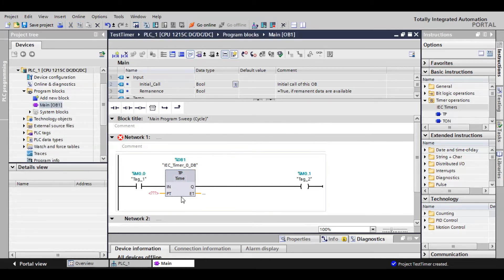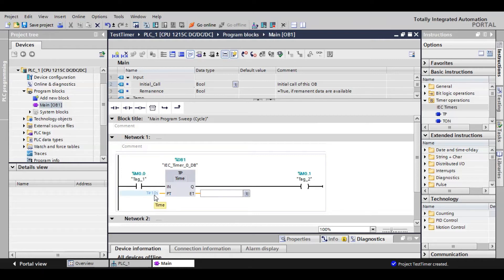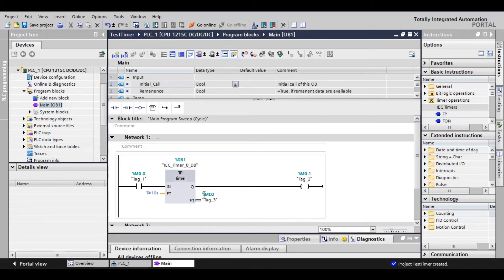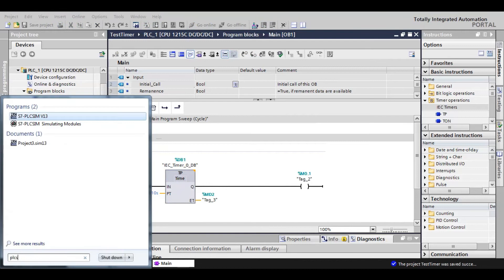As you can see, PT is the value of the time you want the timer for. Let's suppose we want a 10-second timer, so we put in '10s' — this automatically formats the 10-second value. The ET value is the elapsed time output of the timer, not the digital output. Let's give it the address MD2. Now we want to simulate it, so we are going to open PLCSIM V13.